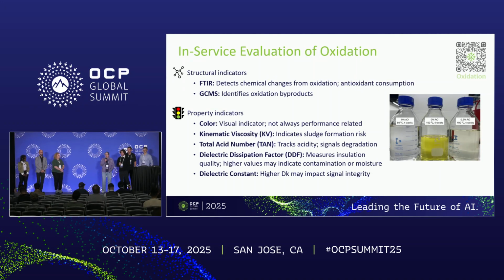For evaluating oxidation in in-service fluids, on the structural side, we recommend using FTIR and GCMS. On the property side, we recommend monitoring color, viscosity, acidity, and also dielectric properties. It's important to note that certain property indicators respond to oxidation at different rates. You may see color change at an earlier rate compared to the dielectric dissipation factor, and other properties such as dielectric constant and viscosity may change at a slower rate. However, we do recommend monitoring these properties while the fluid is in service. This would help folks determine fluid health and when to replace it.